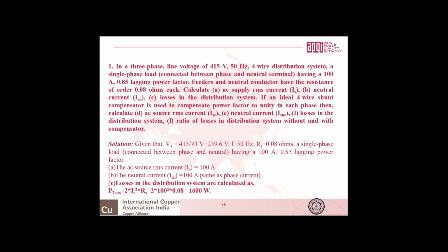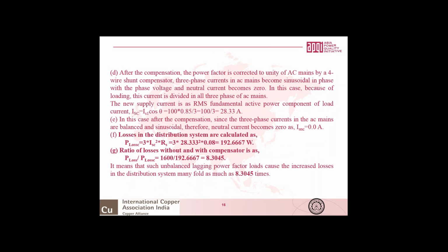That's a resistance of the feeder equal to 1600 watt or 1.6 kilowatt. This is the losses without any compensation in this single phase load connected in 4-wire system. Now, if we use the 4-wire compensator, which is used typically for power factor correction and load balancing, after compensation we expect the power factor is corrected to unity of AC mains by a 4-wire compensator.